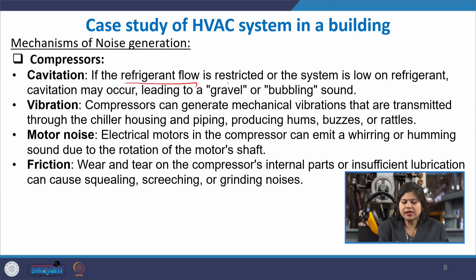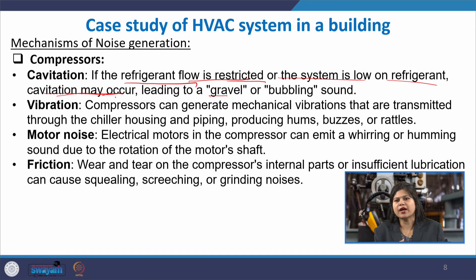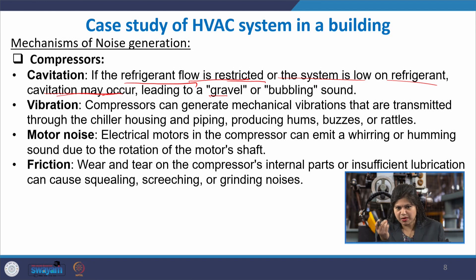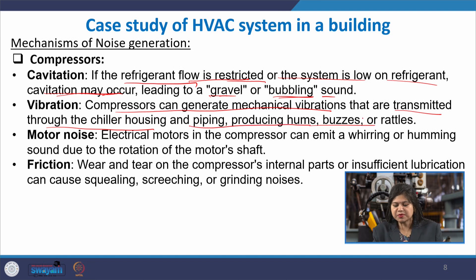Cavitation occurs when liquid flowing through a duct or pipe encounters an obstruction — bubbles form, and you can hear a bubbling noise. Additionally, mechanical vibrations generated by compressors can transmit through the chiller housing to various pipes, producing hums, buzzes, and rattling sounds. Electrical motors in modern compressors can emit a whirring or humming sound due to the rotation of the motor shaft.